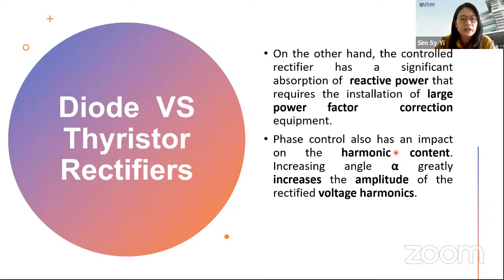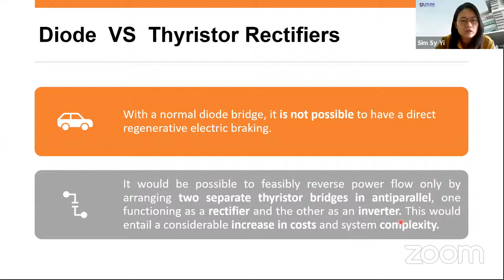But the main thing is that if we are using the diode, it's not possible to have direct regenerative electric braking. So if we're going for electric regenerative braking, we need a thyristor, because we need to arrange two separate thyristor bridges in anti-parallel - one functioning as a rectifier and another functioning as an inverter. This makes the regeneration happen.